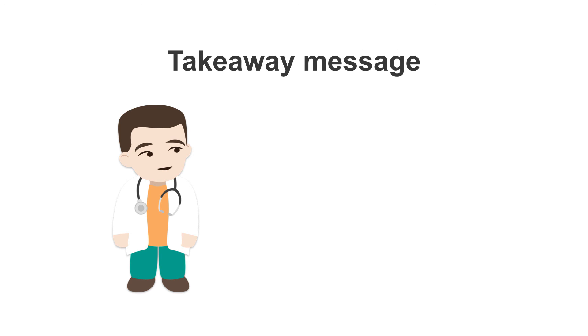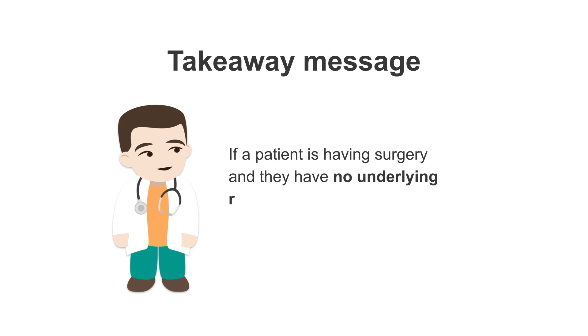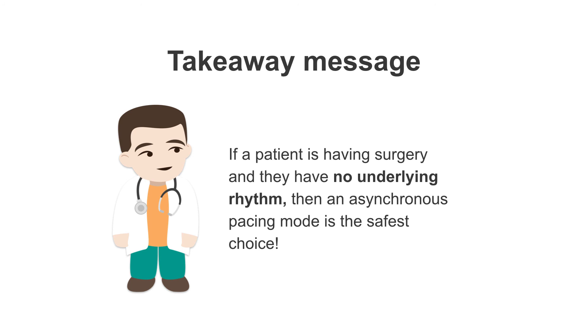So your takeaway message: if a patient is having surgery and they have no underlying rhythm, then an asynchronous pacing mode — AOO, VOO, or DOO — is the safest choice.